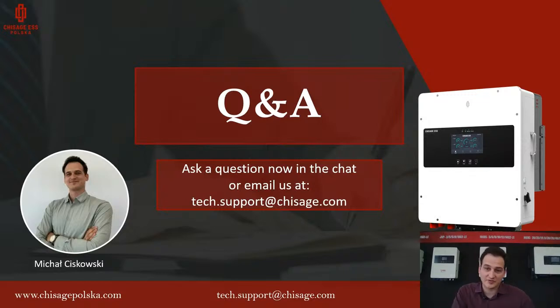From our platform or mobile app, you will see the 5 minute average. For example, the average grid frequency will be 50, but in 1 minute it may be higher than the maximum frequency. So firstly, check if this frequency is okay, and also check your grid settings, whether the maximum frequency is set up correctly. Check what the value is there, and check whether the grid frequency is really higher than it should be.